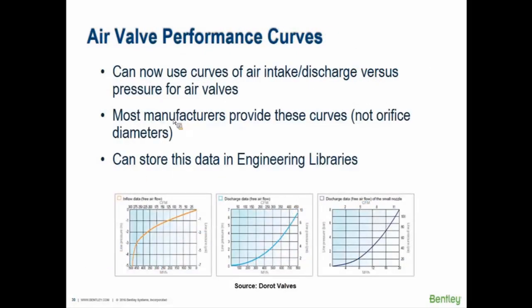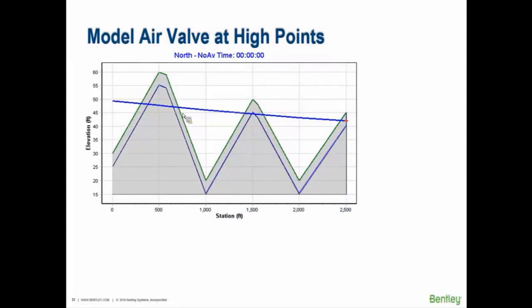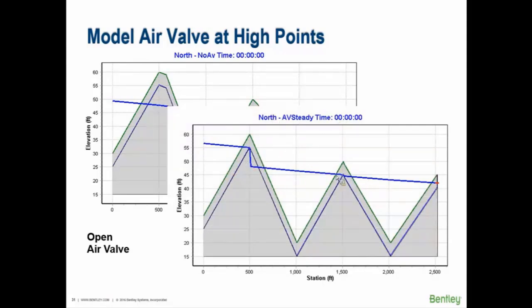Air release valves can also be modeled — added in one of the last Select Series versions and available in the Connect Edition. You size the orifice, and the model determines how quickly air escapes from the line before transitioning to full pipe flow. In this scenario, the air release valve fills and closes, allowing pumping over the top of a hill. You'll need information from the air release valve manufacturer catalog on orifice size and valve operation.